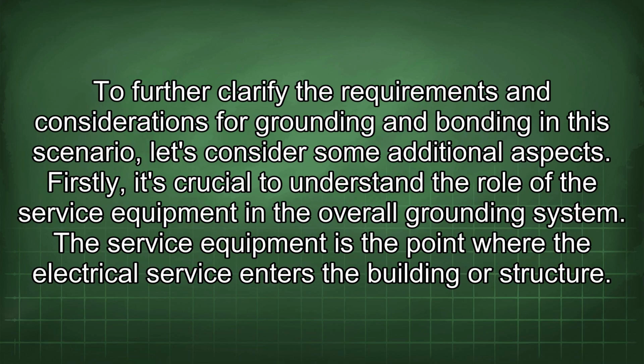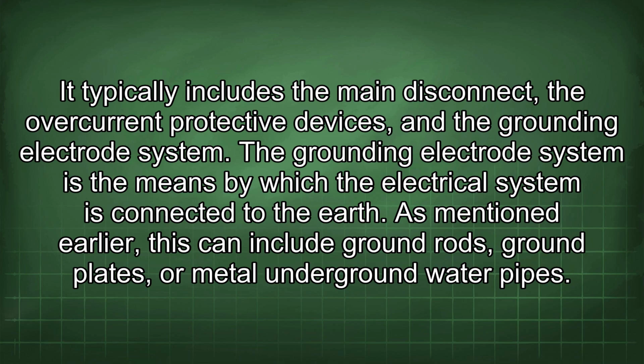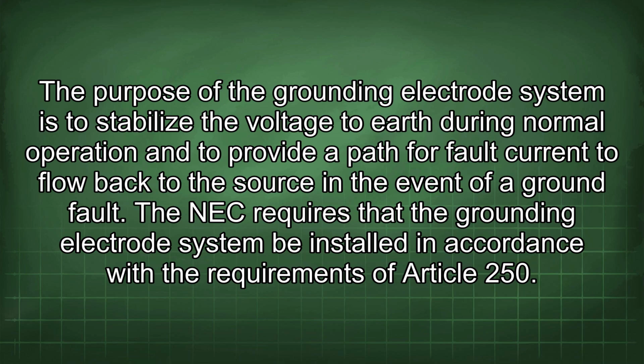To further clarify the requirements and considerations for grounding and bonding in this scenario, let's consider some additional aspects. Firstly, it's crucial to understand the role of the service equipment in the overall grounding system. The service equipment is the point where the electrical service enters the building or structure. It typically includes the main disconnect, the overcurrent protective devices, and the grounding electrode system. The grounding electrode system is the means by which the electrical system is connected to the earth. As mentioned earlier, this can include ground rods, ground plates, or metal underground water pipes. The purpose of the grounding electrode system is to stabilize the voltage to earth during normal operation and to provide a path for fault current to flow back to the source in the event of a ground fault.